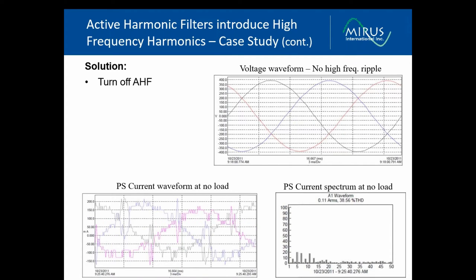We went back to the supplier of the active filter. They tried to change the filters. So all of these devices require passive filters in order to address the harmonics that they're creating. But it didn't help. It helped very little. And ultimately, the only solution was to permanently turn off the active harmonic filter. So they end up with, pardon the pun, a very, very expensive anchor.